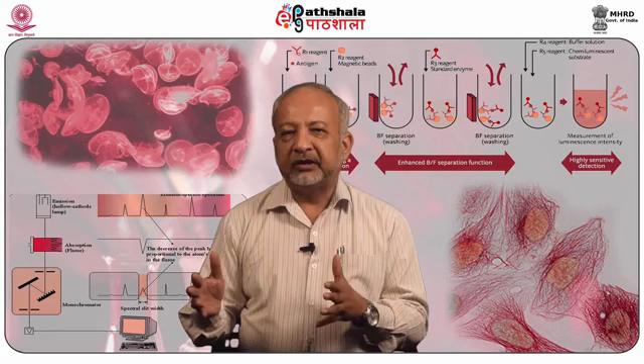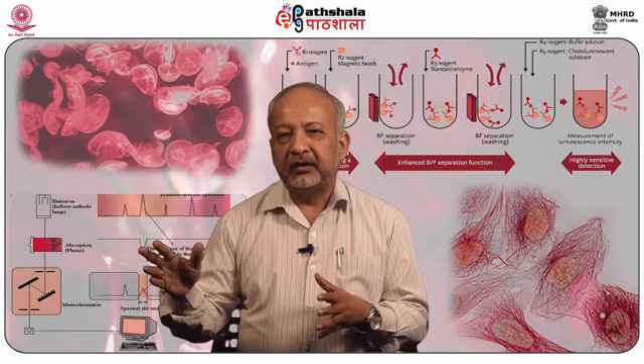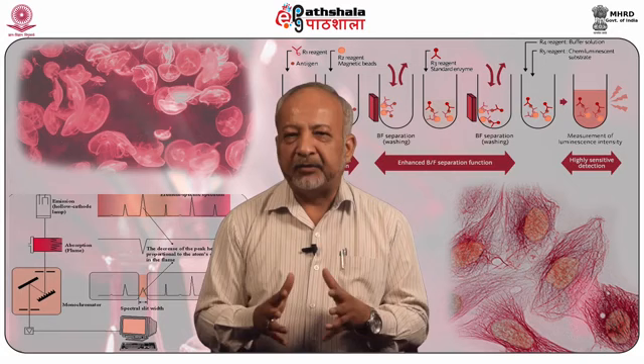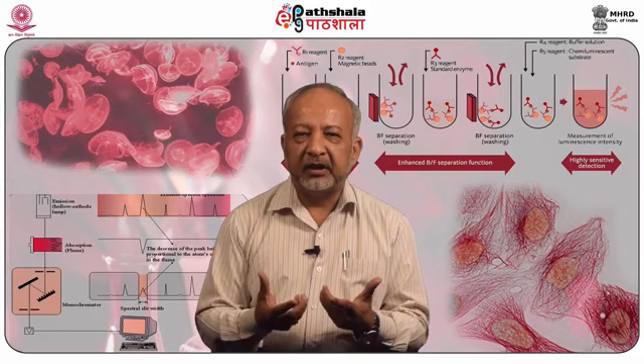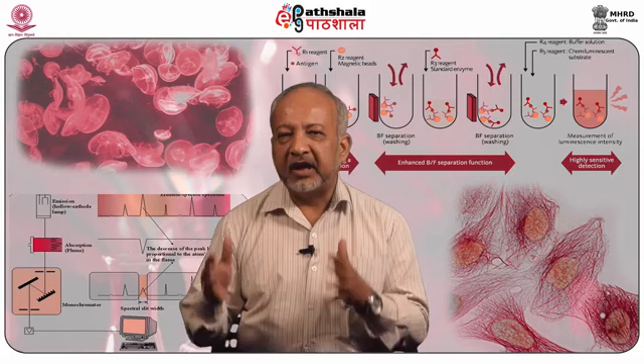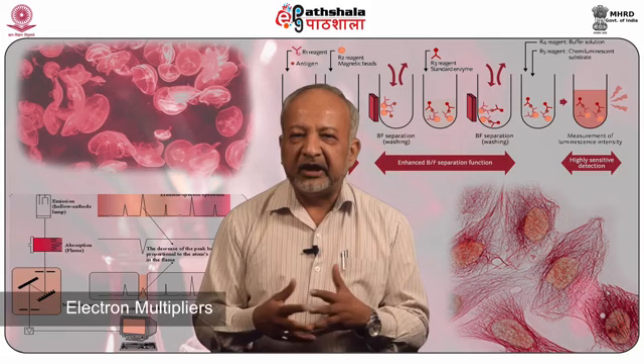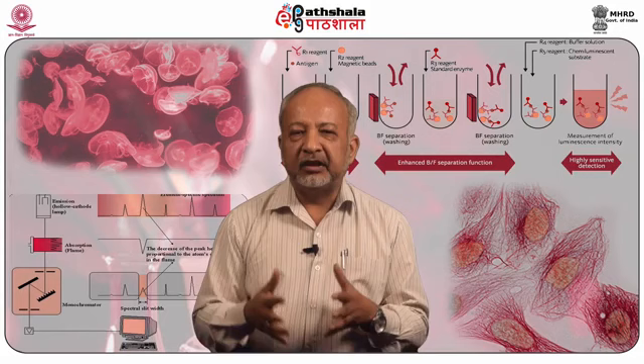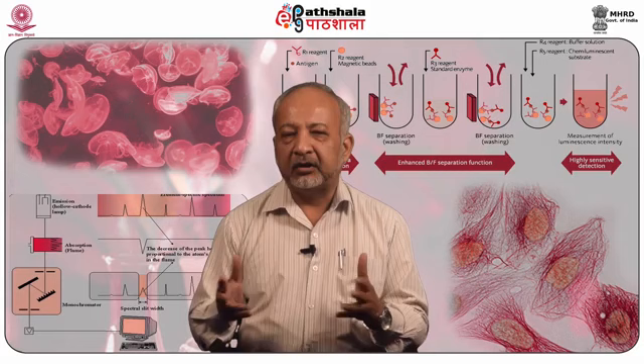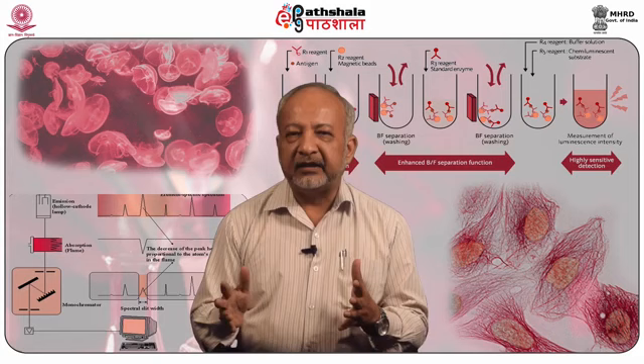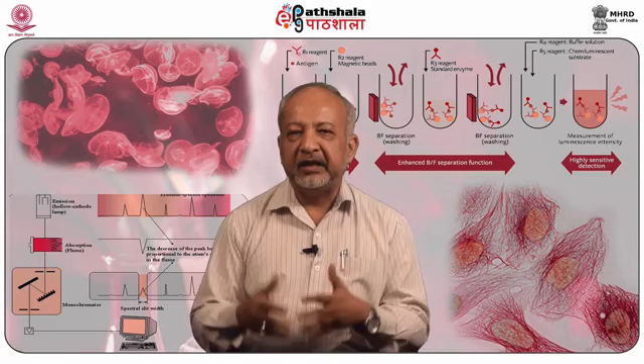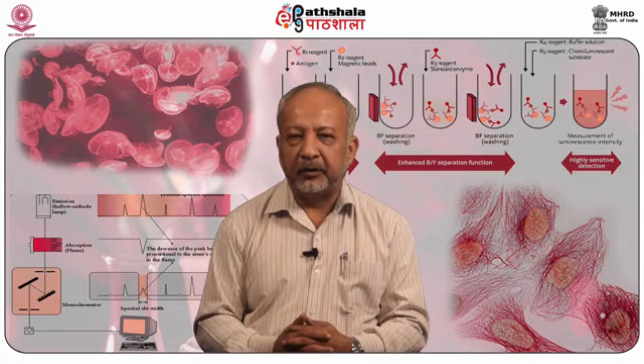The mass spectrometer has a detector where ions are detected after the analyzer. Typically, a metal electrode in a small cup called a Faraday cage or Faraday cup houses the detector. The measurement of detected current by potential drop produced through a large external resistor is recorded in this detector. Electron multiplier dynodes are generally used for organic analytes. Initial impact of energetic ions on the dynode results in emission of electrons, which are then accelerated by the applied voltage into further collisions, resulting in a greatly amplified gain, and the end result is the spectrum that we obtain.